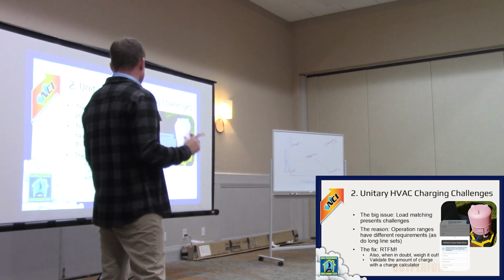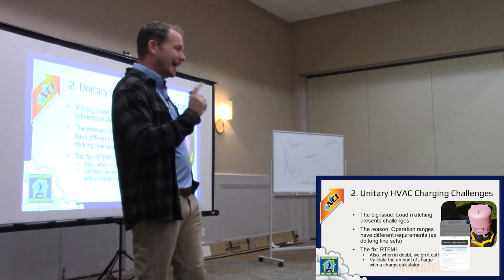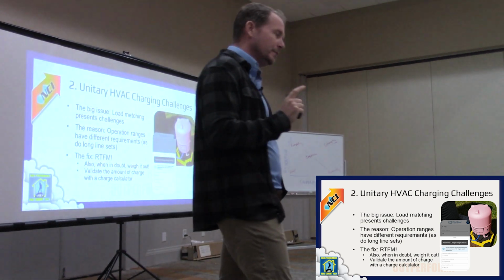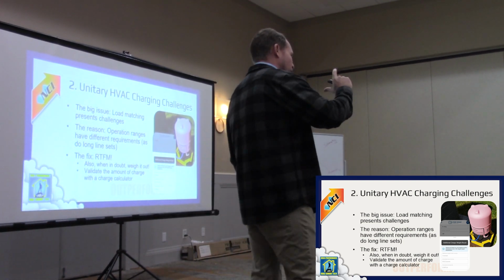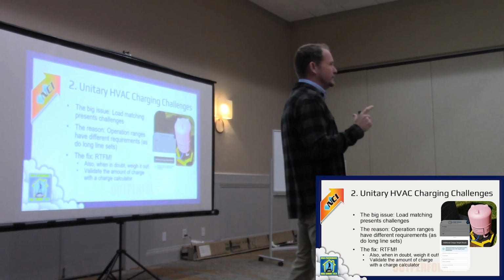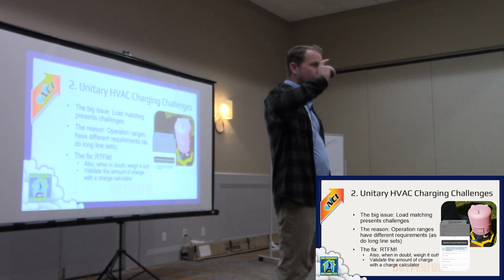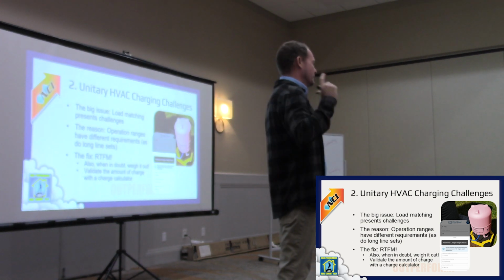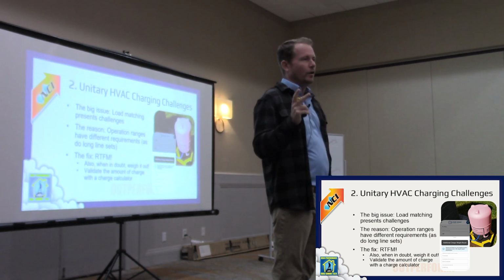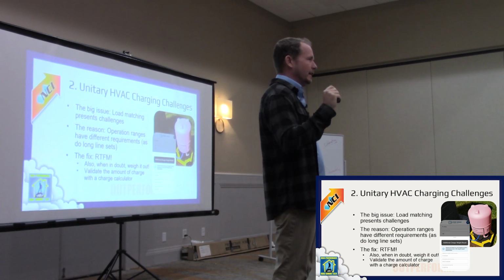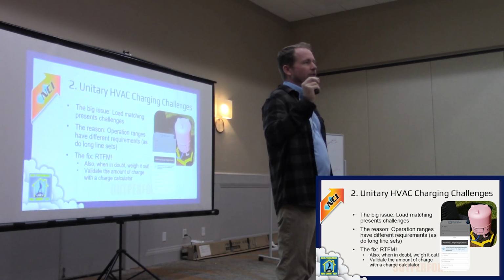In a lot of cases, you're just going to have to weigh it out. There are some good guidelines to follow, but the problem is you have these algorithms built into the equipment that we don't always have full access to - ramping condenser speed, ramping compressor, changing blower, electronic expansion valves - that can be really tricky for your field tech.